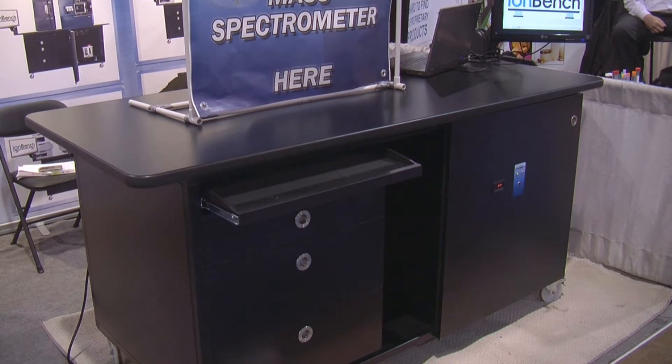The main features of IonBench MS are that the bench is on caster wheels and can be easily moved all around the lab. This provides space saving because we can save more or less 30% space in the lab. It also allows easy servicing of the mass spec — you can easily push and pull the bench against the wall.